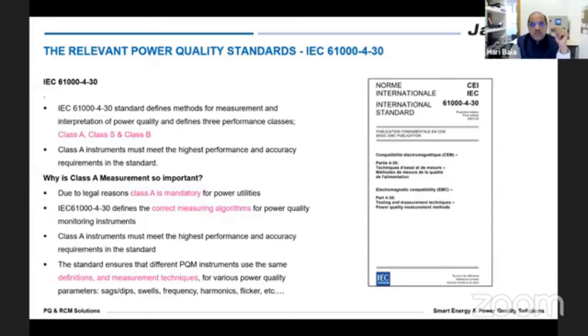Class A becomes mandatory for legal compliance, because Class A is the one which tells us how these measurements are done specifically for every parameter. The Class A standard must meet high performance and accuracy requirements. So all the instruments have to be very reliable and have a standard way of calculating the parameters and giving them out as per the standard.